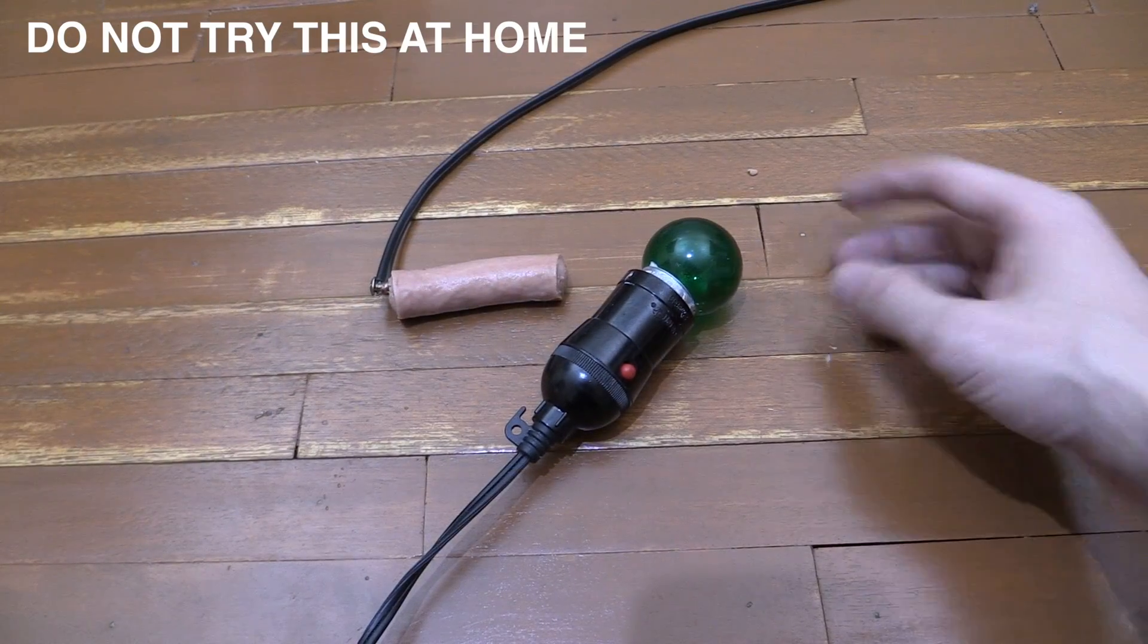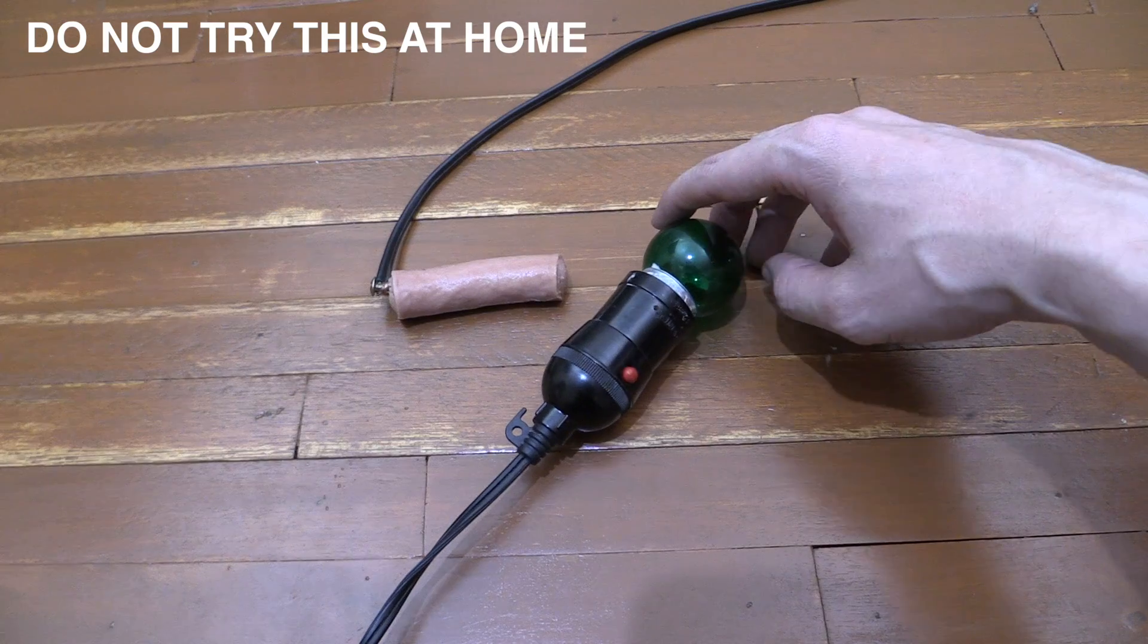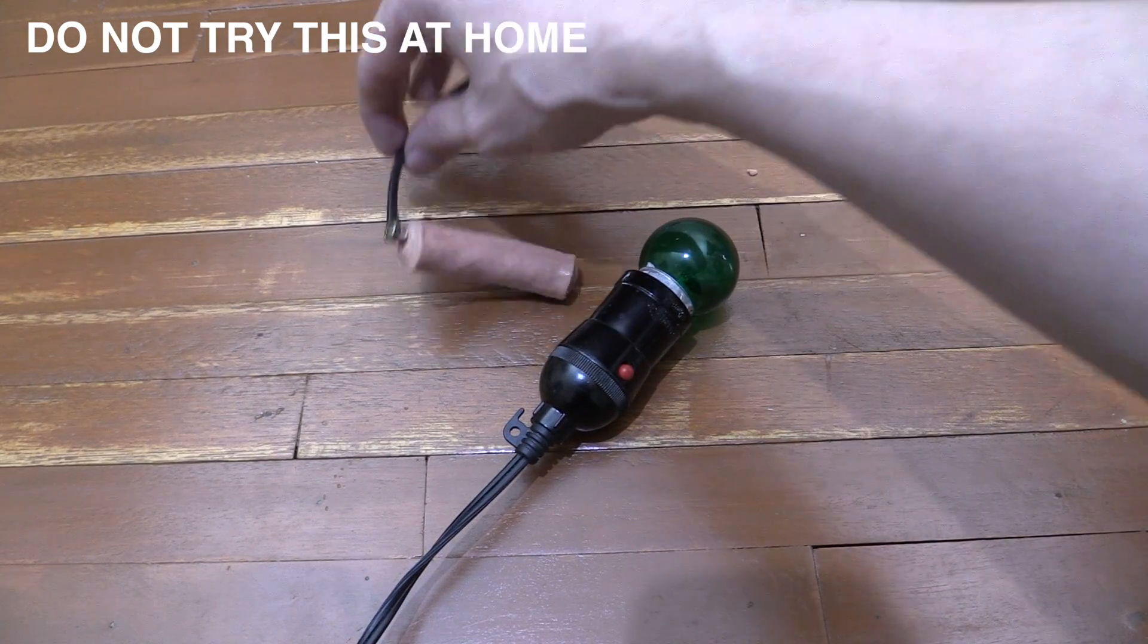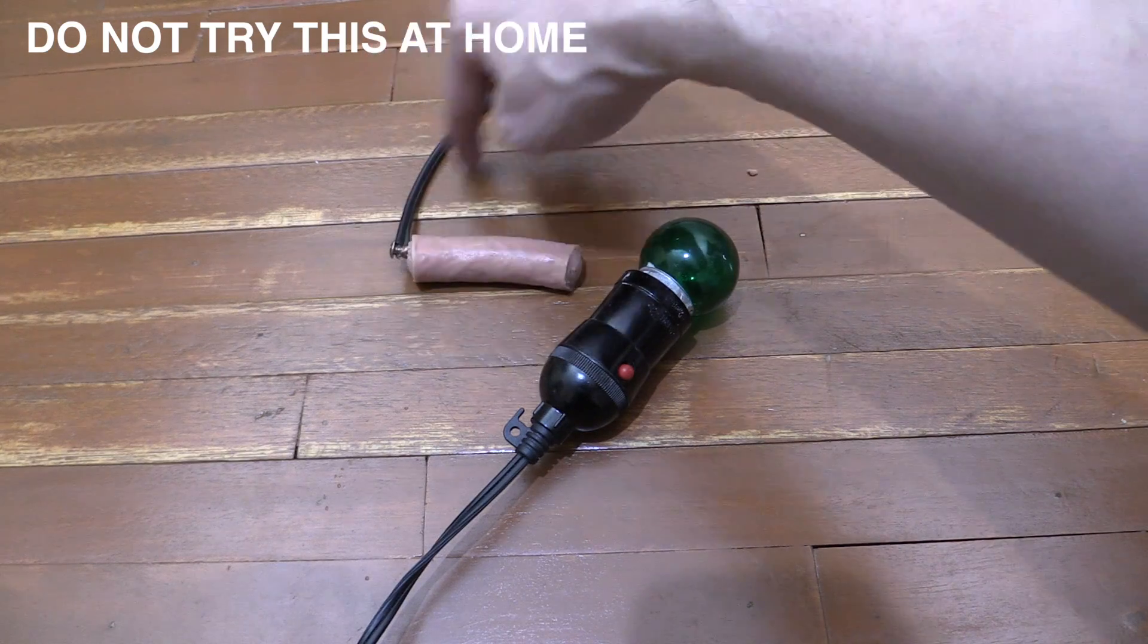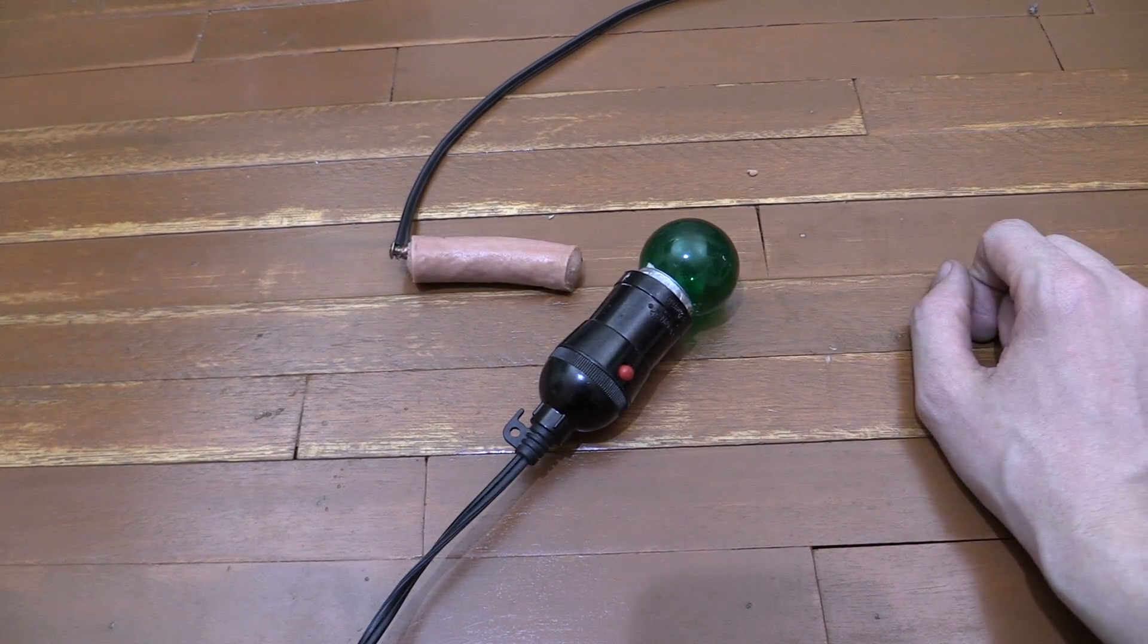So we're going to do a real-life test now. This is the bulb holder where I had the shock before from touching the metal. Instead of using my finger, we're going to test with a hot dog and I do have a wire going into that. That's just ground, so basically I've grounded the hot dog just like it was a human finger. So let's see what happens when we don't have any GFCI protection.